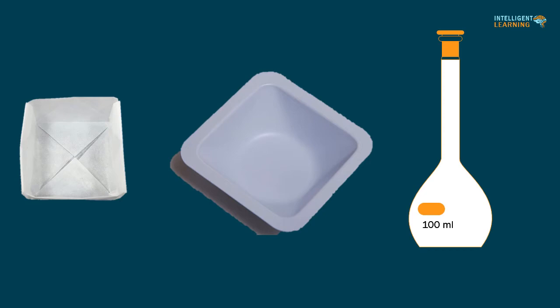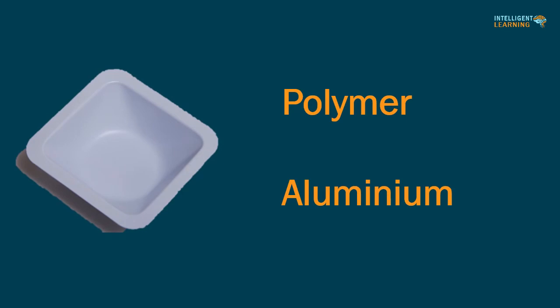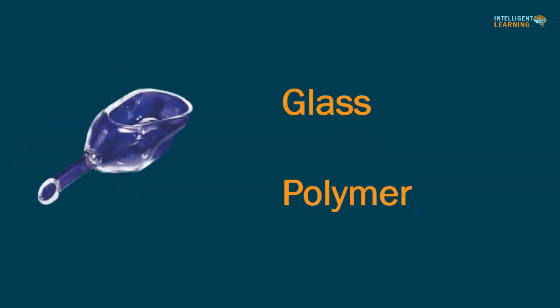Hygroscopic papers are not recommended for weighing because they may have a detrimental effect on the observed results. Weighing dishes typically are constructed from a polymer or from aluminum. Weighing funnels typically are constructed from glass or from a polymer. The design of this type of receiver combines attributes of a weighing dish and a transfer funnel, which can simplify the analytical transfer of a weighed powder to a narrow-necked vessel such as a volumetric flask.